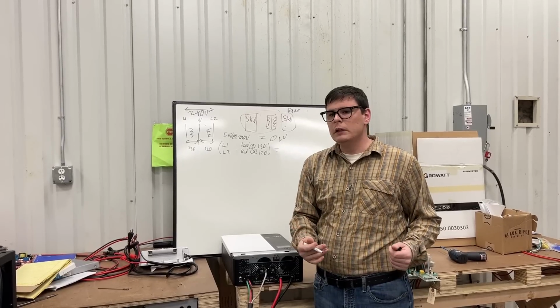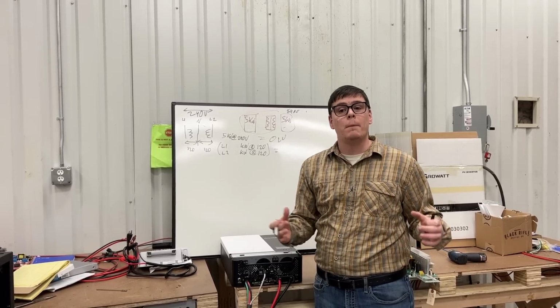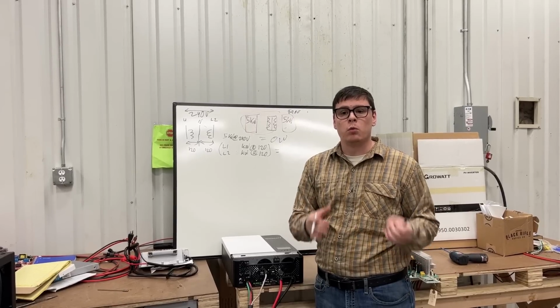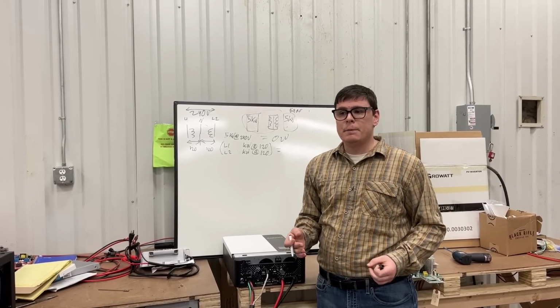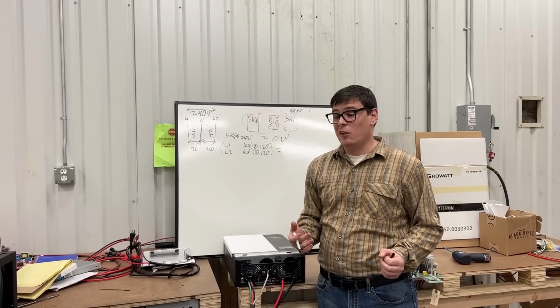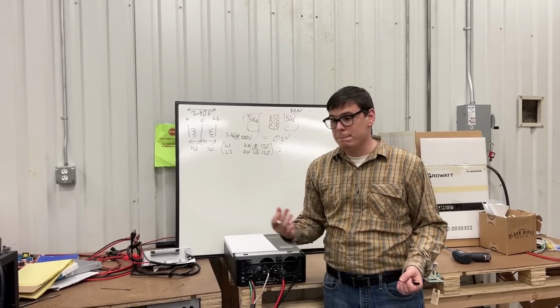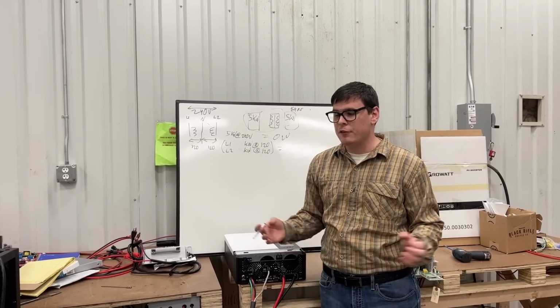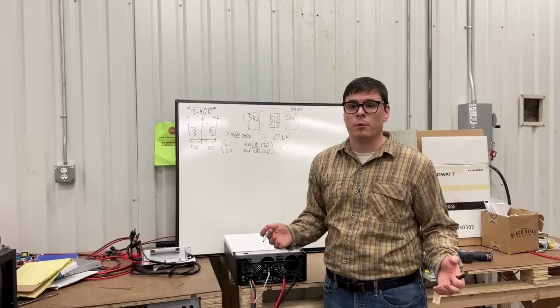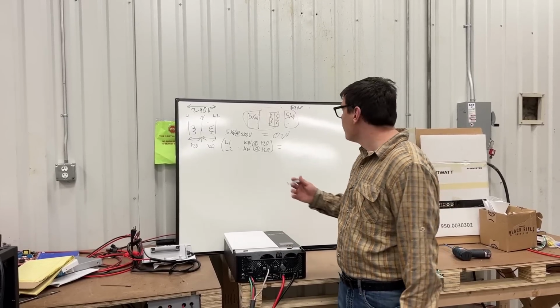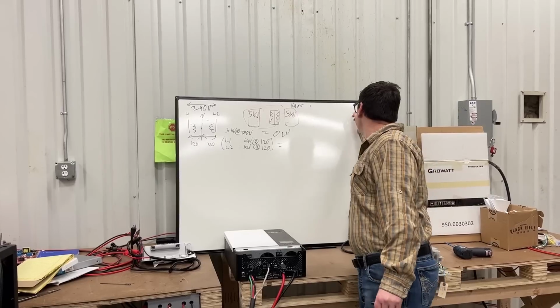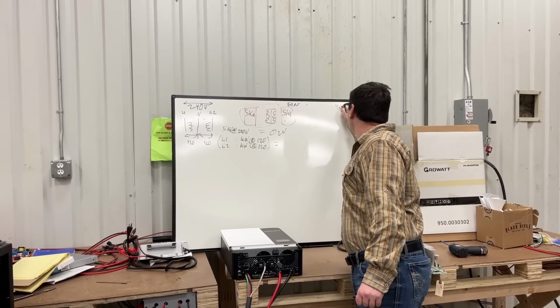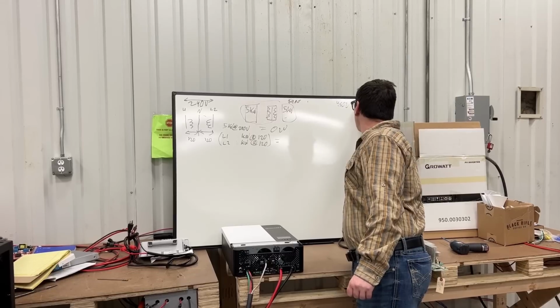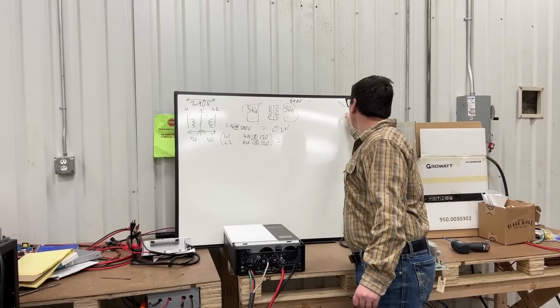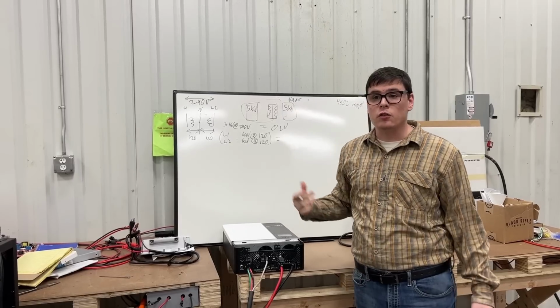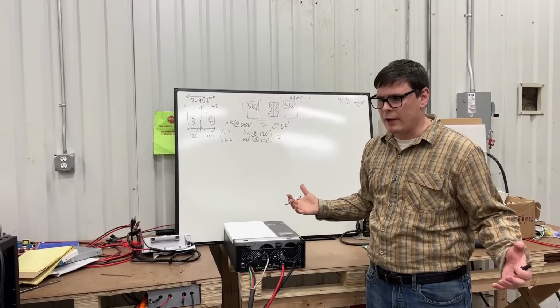And so, unless you have an inordinate amount of 120s that you intend to be running, resistive 120 loads, which typically eat a lot of kilowatt hours, it's really hard to build a system on that. But if it's what you're bent on having, you're welcome to buy more transformers from us. But the flexibility of this system is you get the 450 volt charge controller, and you don't have to pay for things you don't need. You just buy a 240 volt inverter board, and that's all you've got to have.